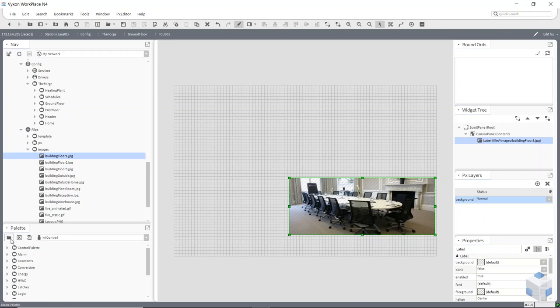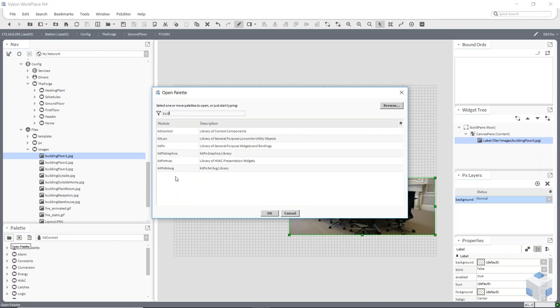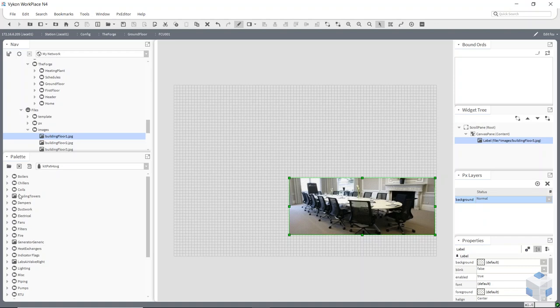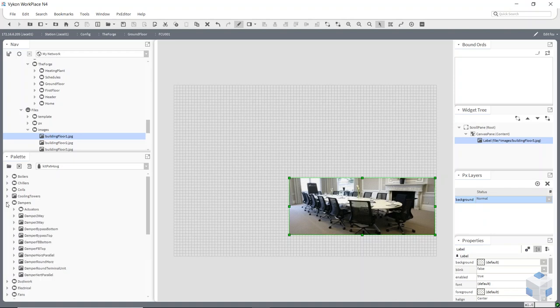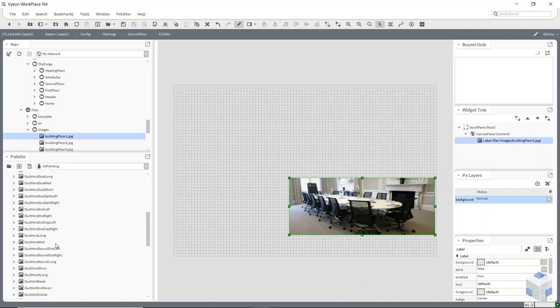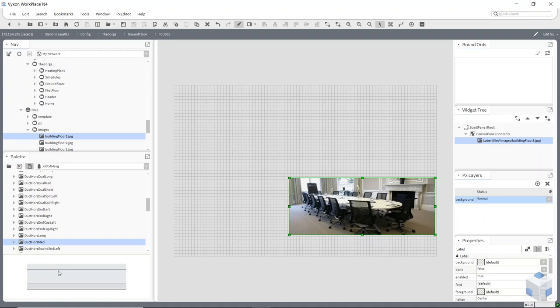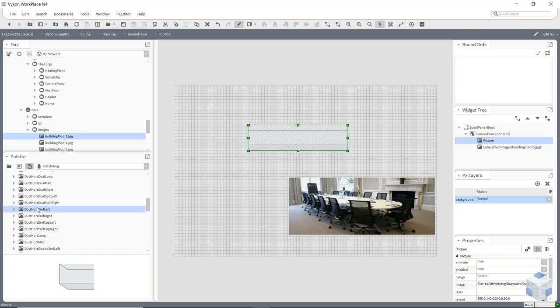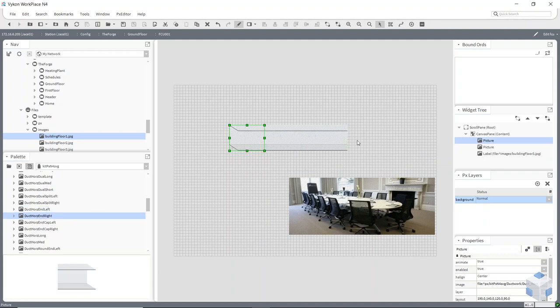There's also a palette for our graphics. If you go into the kits and type in 'kit', these are all different kits set up for us. The latest one is called Kit PXN4SVG. In here we have lots of different images — some are flat images with no animation, some are animated, some are for numeric points, and others are for boolean points. I'll drag some ductwork onto my canvas. There's a preview button so you can see what it will look like. I want duct horizontal medium — drag from left to right and place it where you want.